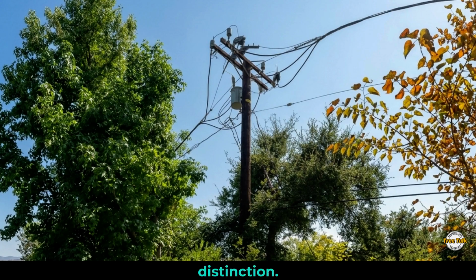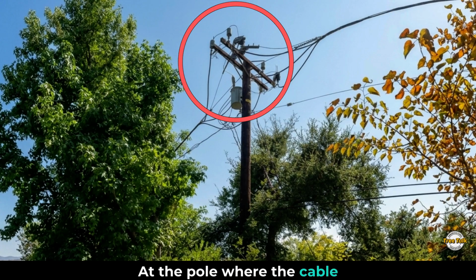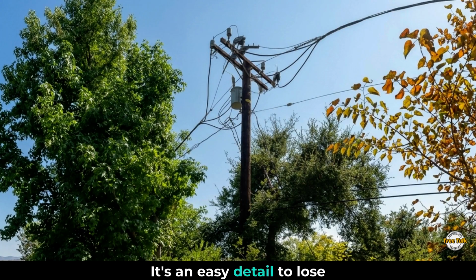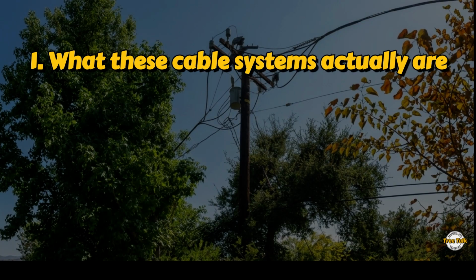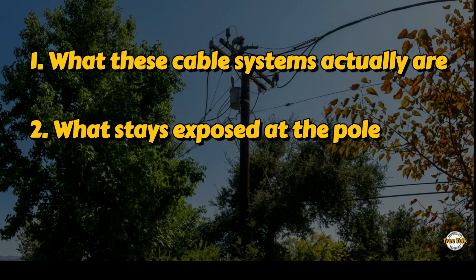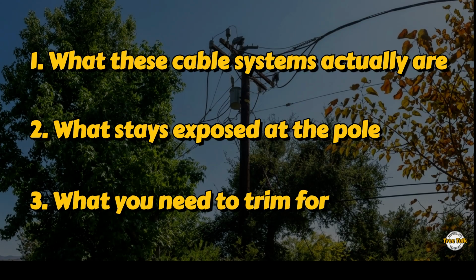Here's the important distinction. That reduced clearance rule only applies to the covered wire itself. At the pole, where the cable connects to hardware, that protection disappears. The connection and the equipment there are exposed and energized, just like on any bare-wired pole. It's an easy detail to lose track of if you're used to these systems being more forgiving along the span. Today, we're going to cover what these cable systems actually are, exactly what stays exposed at the pole, and what you need to trim for.